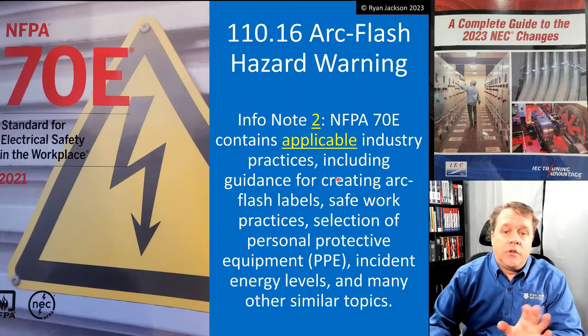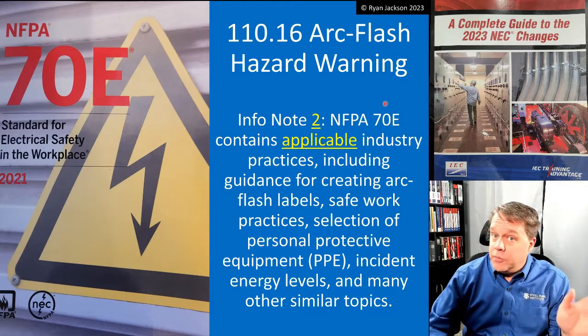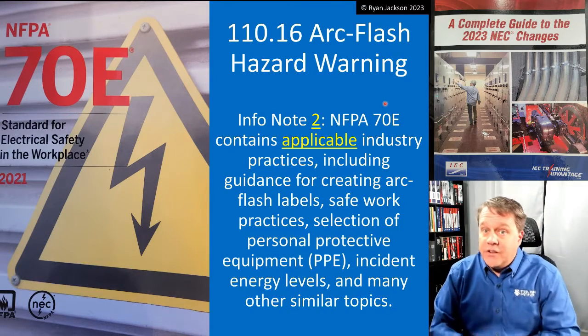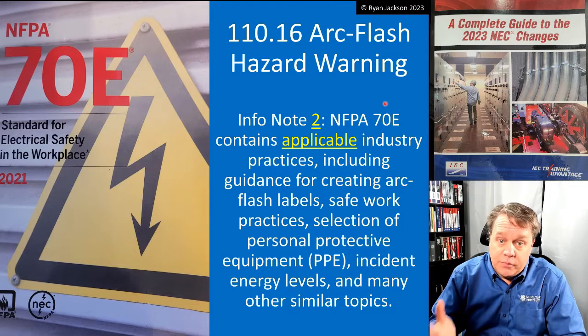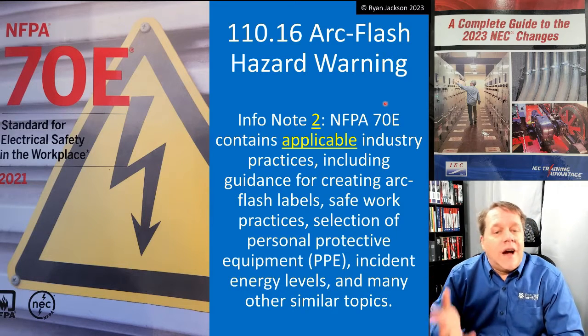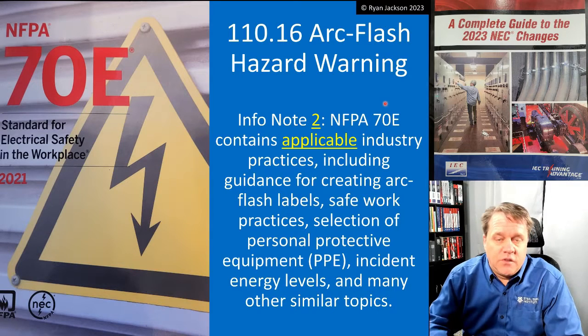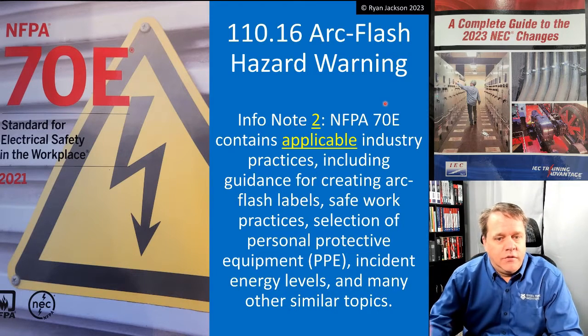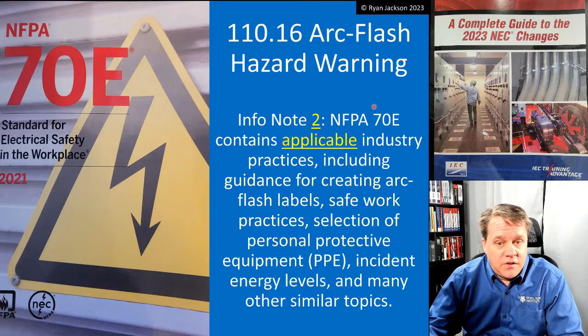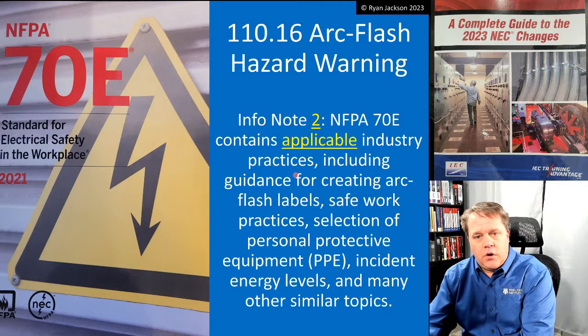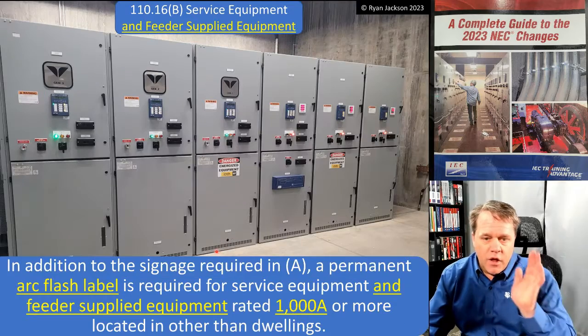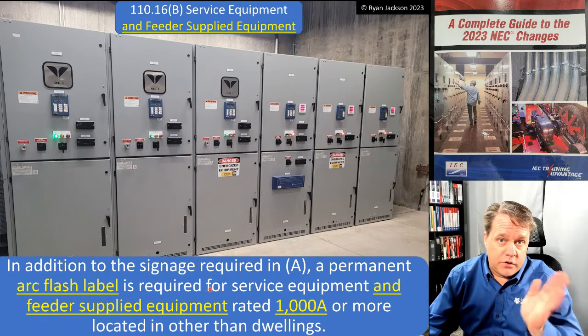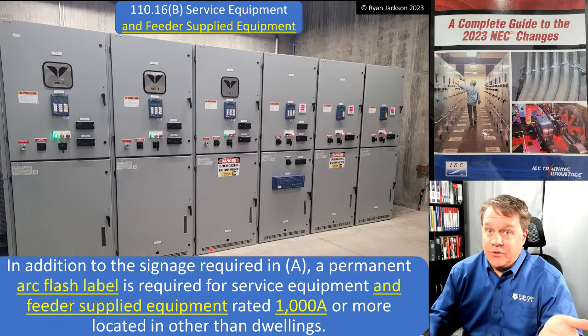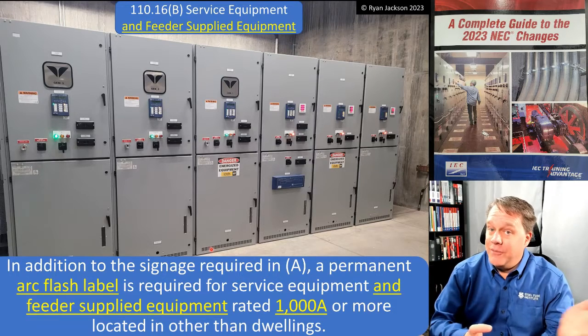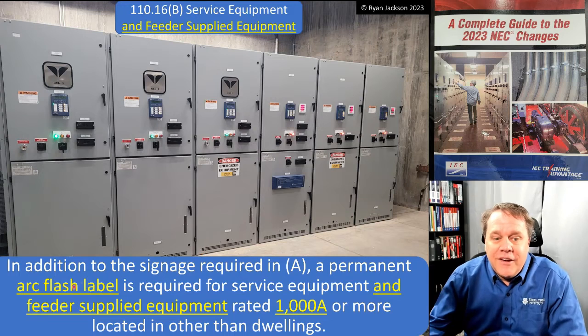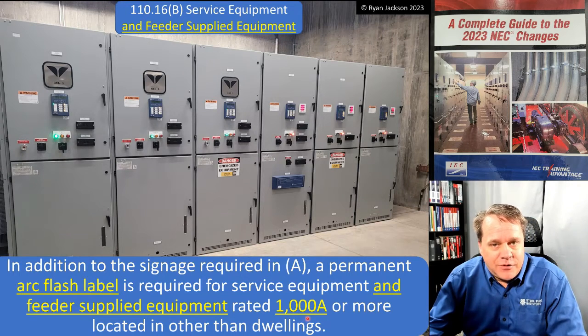Now, there's an informational note that they revised that says, listen, if you don't know what an applicable industry standard is, here's an example, NFPA 70E. That's an applicable industry standard. It has guidance for creating arc flash labels, safe work practices, selection of PPE, incident energy levels, and other similar topics. All right, so there is your informational note. So again, 1,000 amps or more, supplied by a service or a feeder, which once you get over 1,000 amps, you're probably going to be supplied by a service or a feeder. Full-blown arc flash label, 1,000 amps or more. There you go.